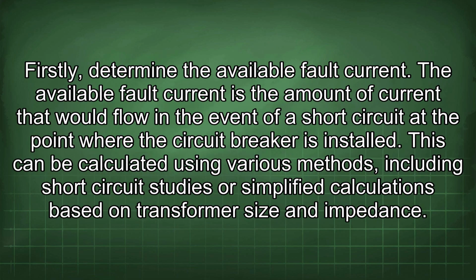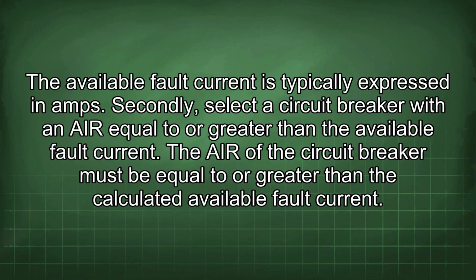Firstly, determine the available fault current. The available fault current is the amount of current that would flow in the event of a short circuit at the point where the circuit breaker is installed. This can be calculated using various methods, including short circuit studies or simplified calculations based on transformer size and impedance. The available fault current is typically expressed in amps.